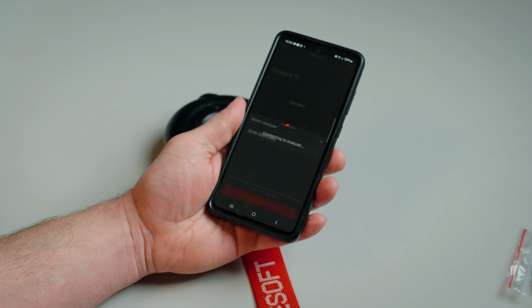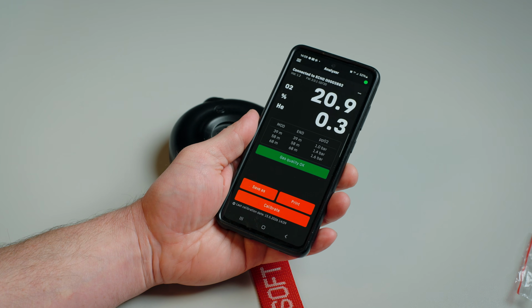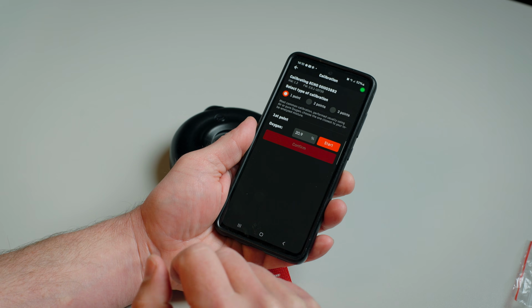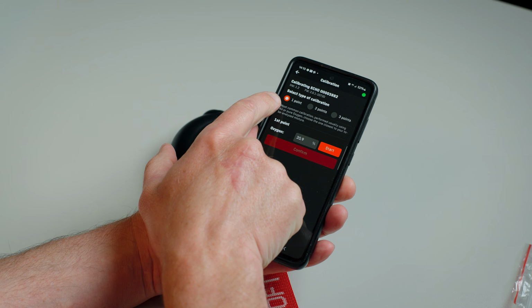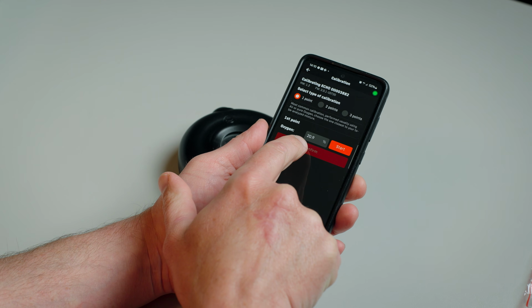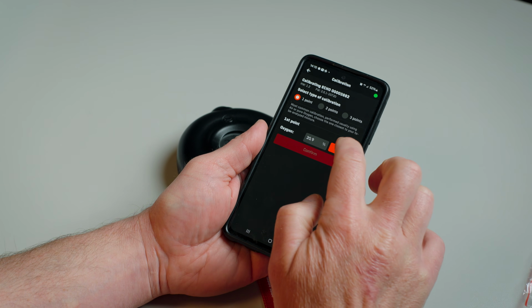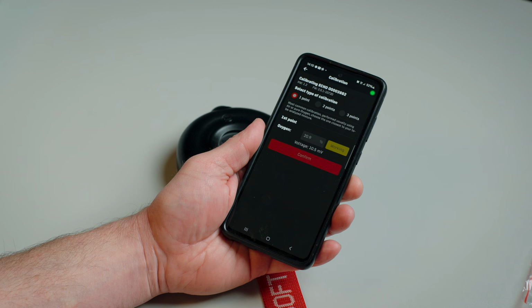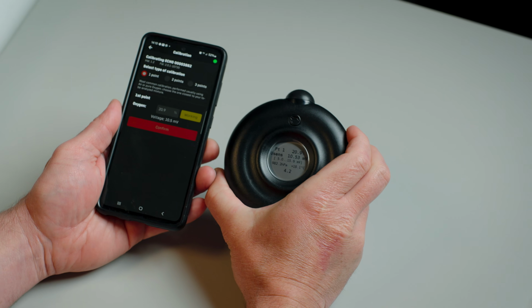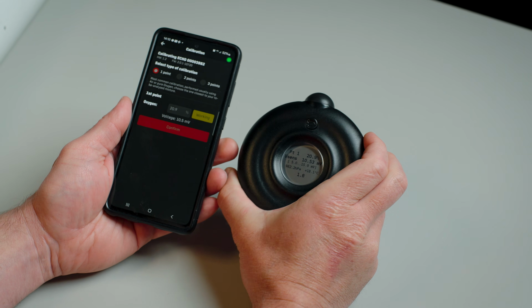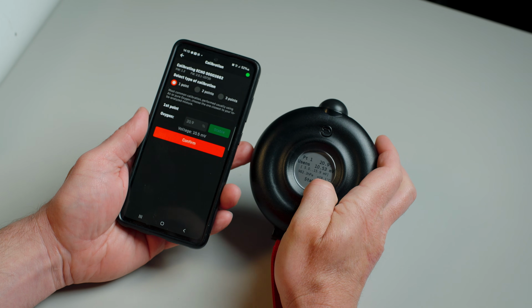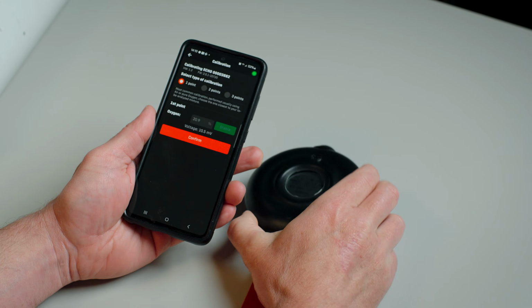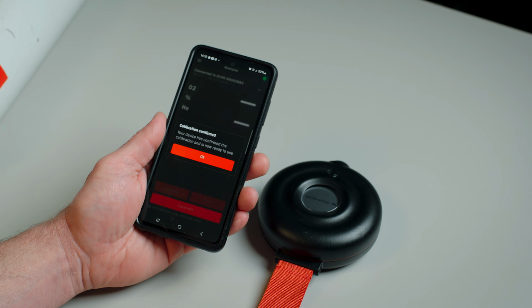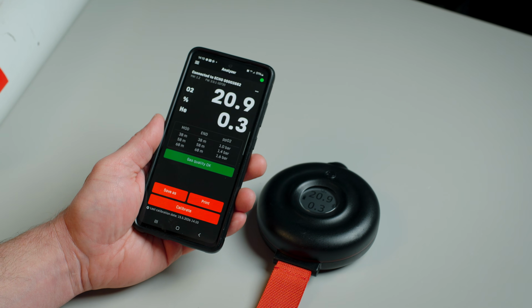We can calibrate Echo also with the app. So we open the analyzer tile. Now it's connecting with the analyzer and we press calibrate. We have a 1-point calibration now with air, so it's 20.9% of oxygen. We press start and wait for calibration. You can see also here that it communicates and Echo waits for stabilization. When it's stable, we press confirm and Echo is calibrated.